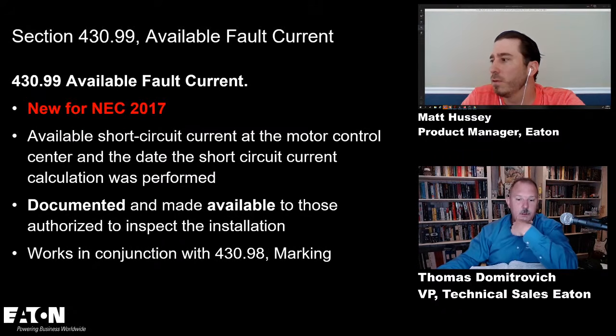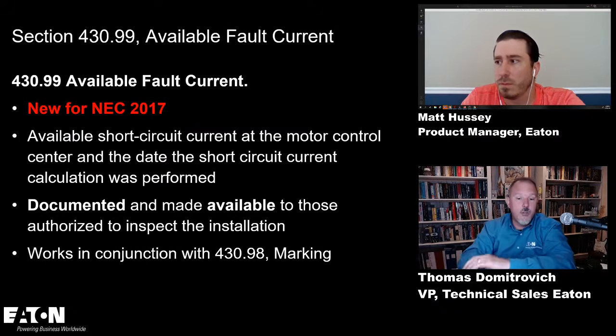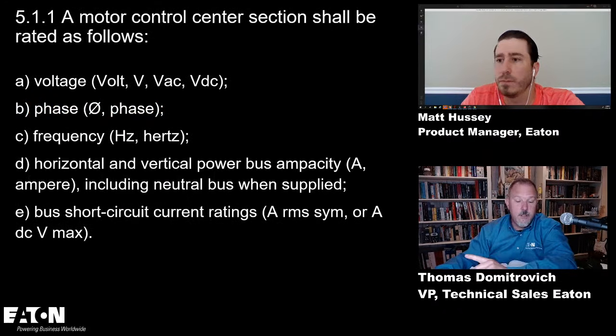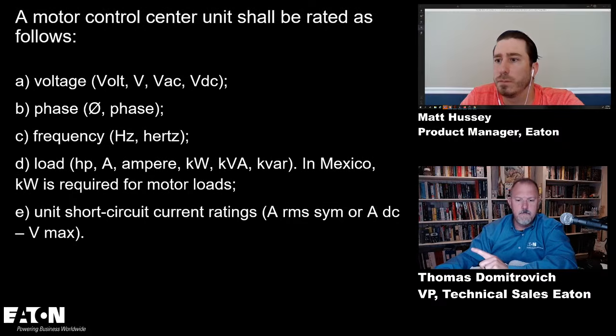430.99 is the available fault current. This is new for the 2017 code: the available short circuit current at the motor control center, and the date the short circuit current calculation was performed, has to be documented and made available. So that's an important new requirement in the 2017 code. And that didn't change in the 2020 code.